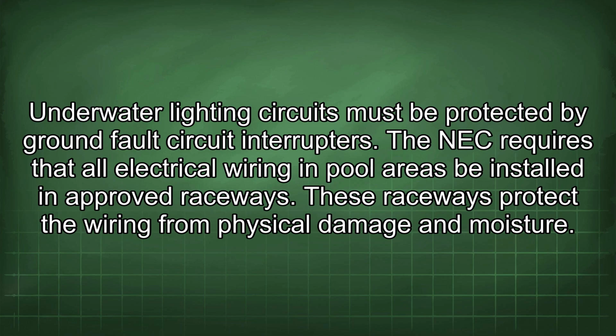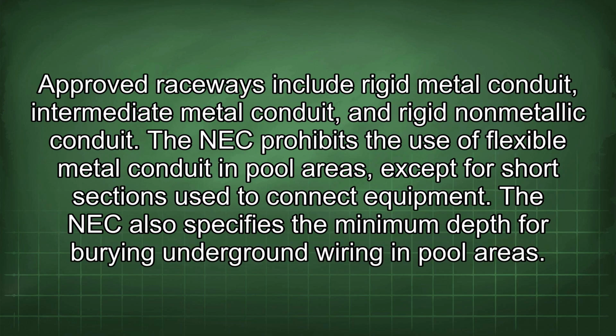The NEC requires that all electrical wiring in pool areas be installed in approved raceways. These raceways protect the wiring from physical damage and moisture. Approved raceways include rigid metal conduit, intermediate metal conduit, and rigid non-metallic conduit. The NEC prohibits the use of flexible metal conduit in pool areas except for short sections used to connect equipment.